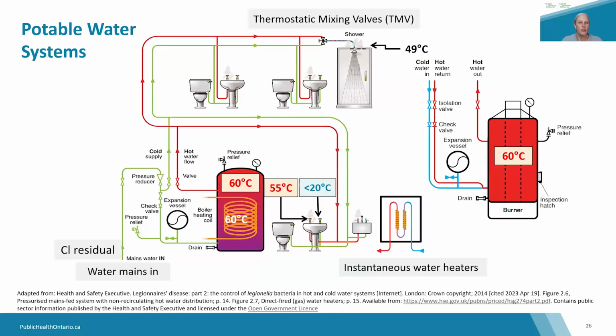So this image shows somewhat of a simplified schematic of a recirculating potable water system, depicting the recommended temperatures at various locations in the system. So to prevent the conditions that would allow Legionella growth, it's recommended that cold water temperatures are maintained below 20 degrees Celsius. Hot water heater or tank temperatures are maintained above 60 degrees Celsius. And the hot water temperatures distributed throughout the system to the endpoint or the point of use should ideally exceed 50 degrees Celsius, with some recommending above 55 degrees Celsius in healthcare facilities.